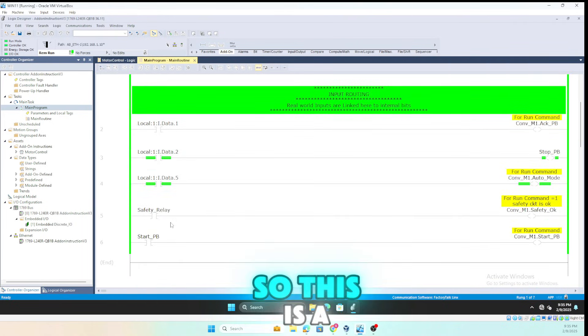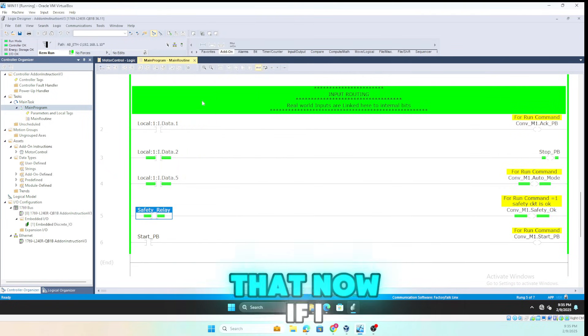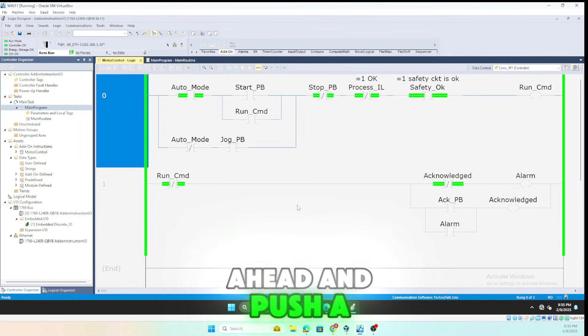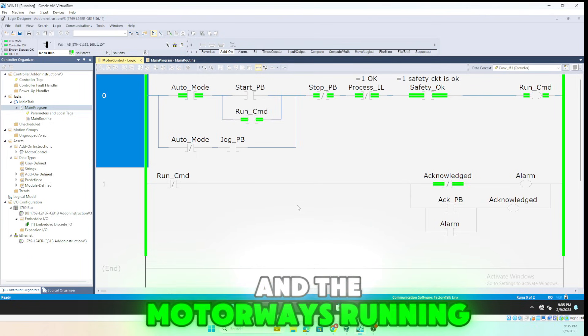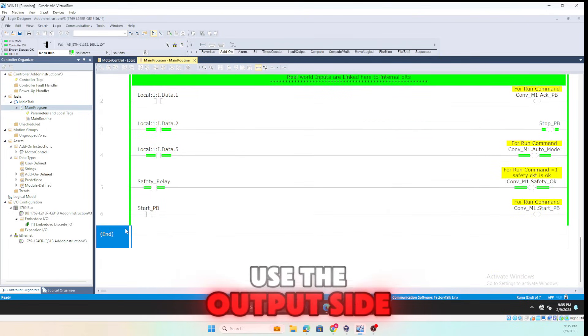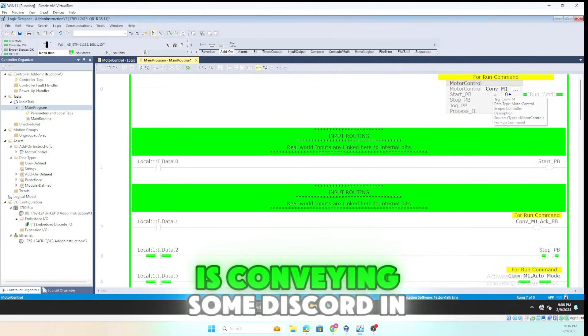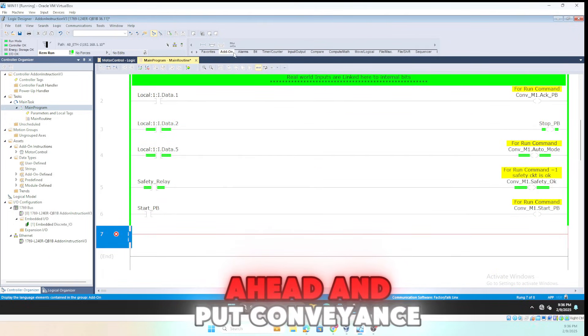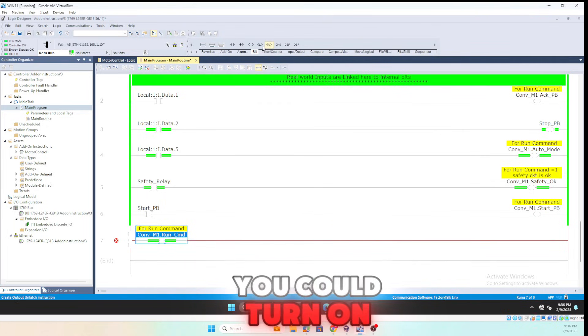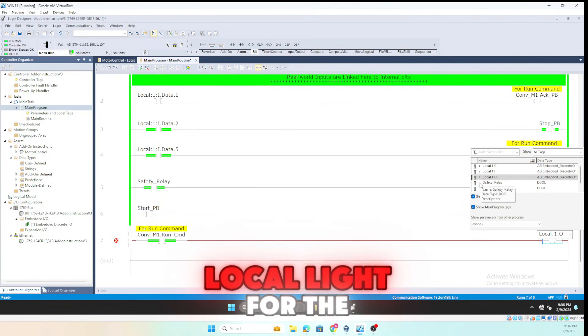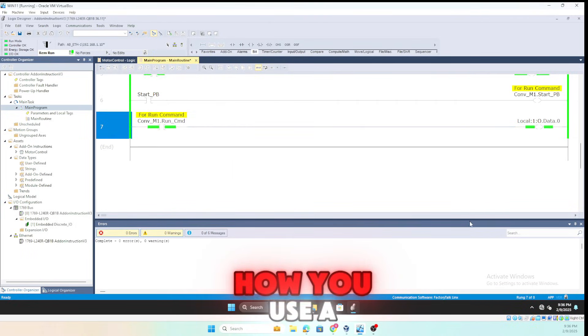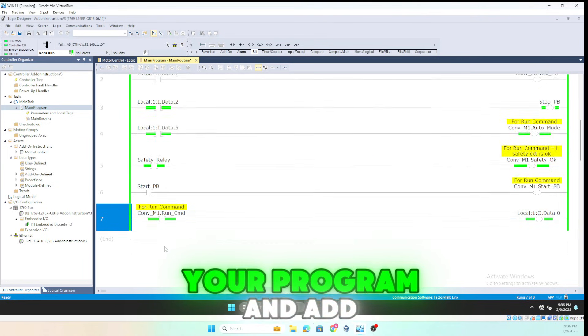We need to give it safety first — it's a memory tag, so we toggle it. Going back to auto mode, we're now waiting on a start push button. We push the start button and we have a run command — the motor is running, and you can see it on the display. You can also use the output side of the AOI: put Conveyance_M1.run_command on your ladder and turn on a light on your PLC for a local display indicator that the motor is running.